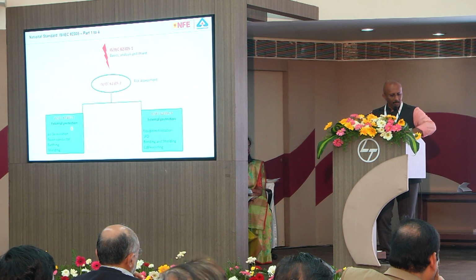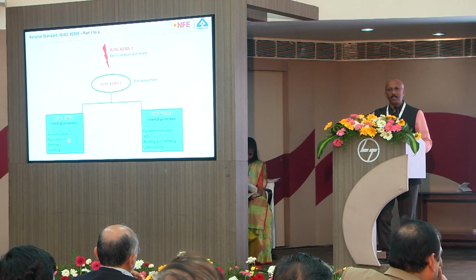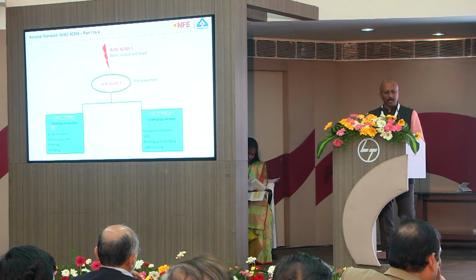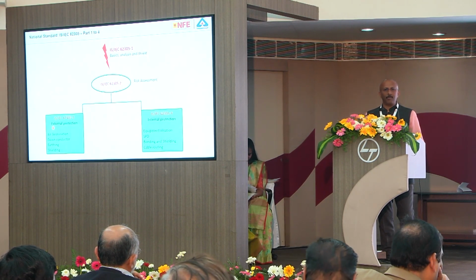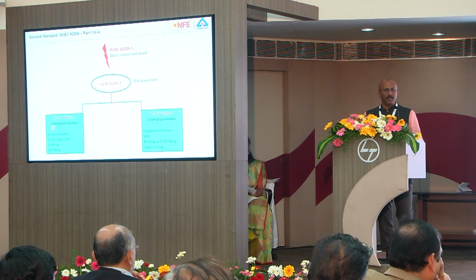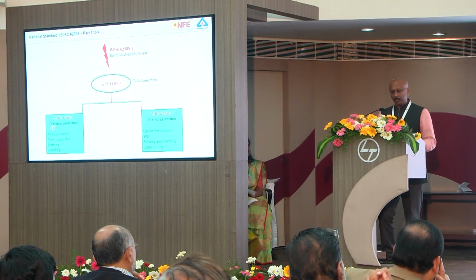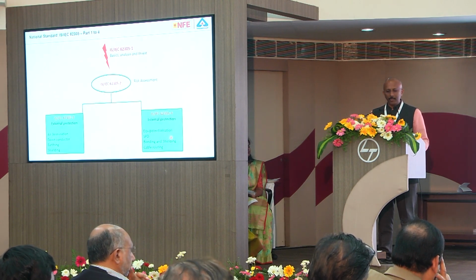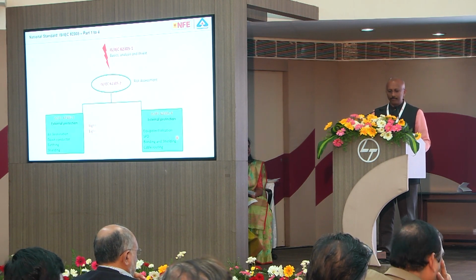62305 talks about air termination, down conductors, earthing and shielding. This means a building will be protected against lightning, and if you have all these, air termination, down conductor, earthing and shielding, if the number 4 is not available, of course your electronics will fail. In most buildings, air terminations are there, I have pictures I will show you. Then with respect to internal protection, you need to have equipotential bonding, SPDs, equipotential bonding with the help of SPDs sometimes, then bonding and shielding and cable routing.